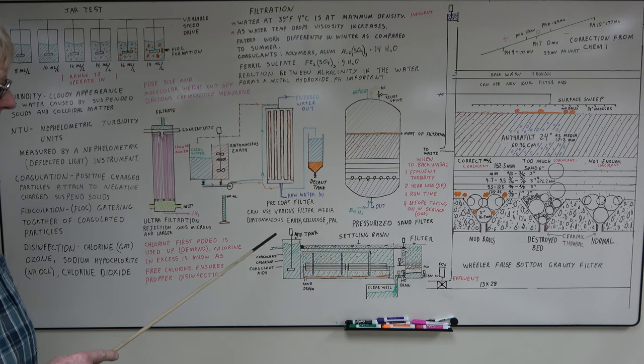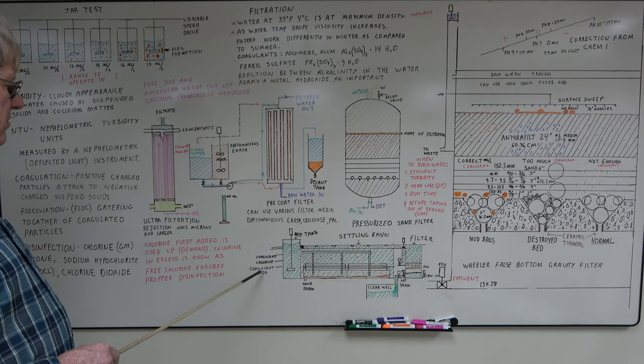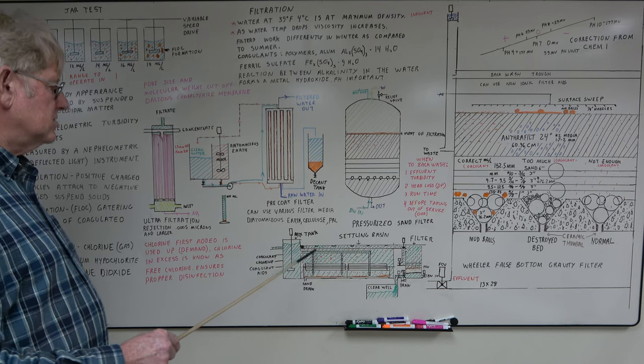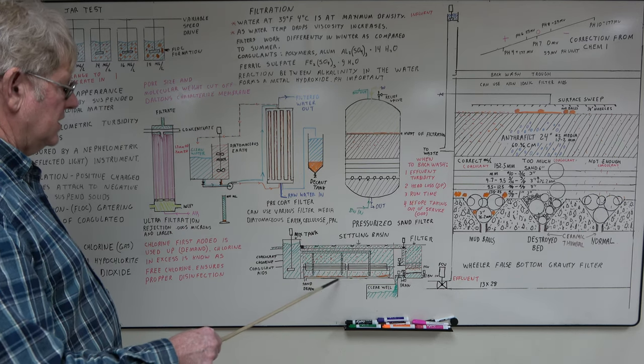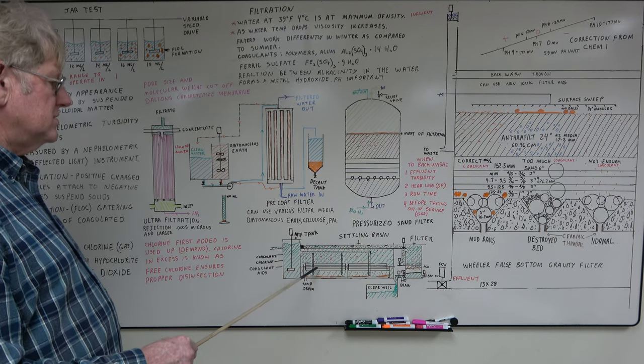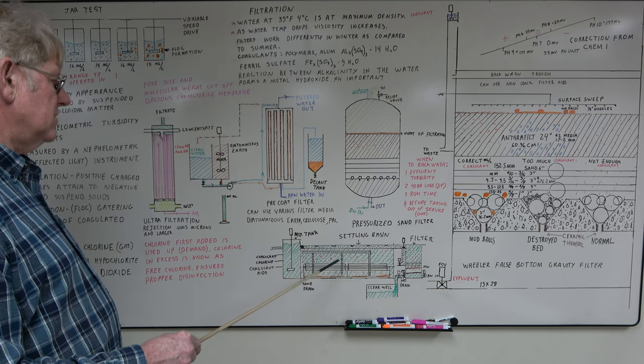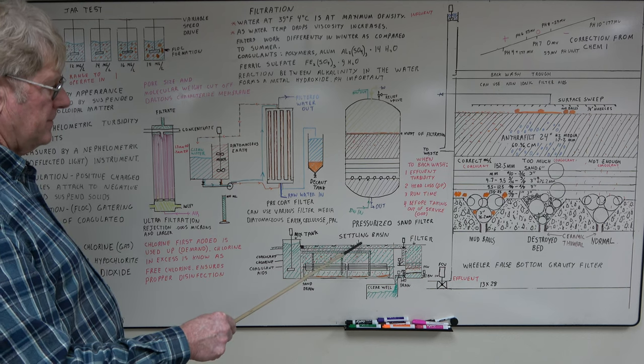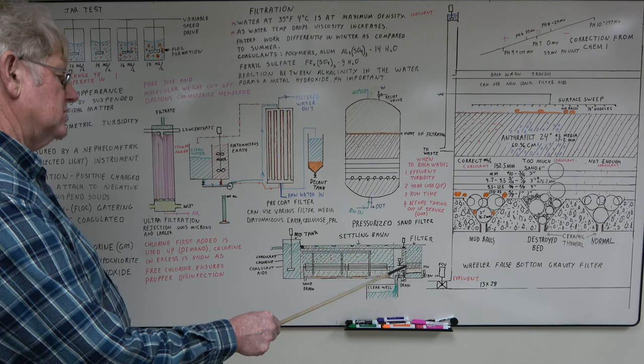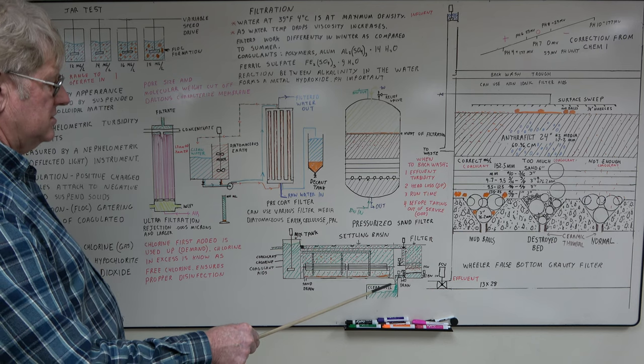This diagram shows a plant using gravity filters. You have your coagulate coming in. Chlorine, coagulant aids. Raw water coming in goes to a mix tank. Chemicals are mixed up. From here it goes out to the settling basin. It drops down to the bottom. You have paddle wheels that slowly mix the water, try to form good floc formation. The whole purpose of this is to make good floc formation and get all the particulate large enough to come out in the filter. On the top you'll have your trough that collects the water and it goes over to your filter where the particulates remove the floc. From there it flows down to a clear well. This will be the filtered water that's sent to the distribution system.